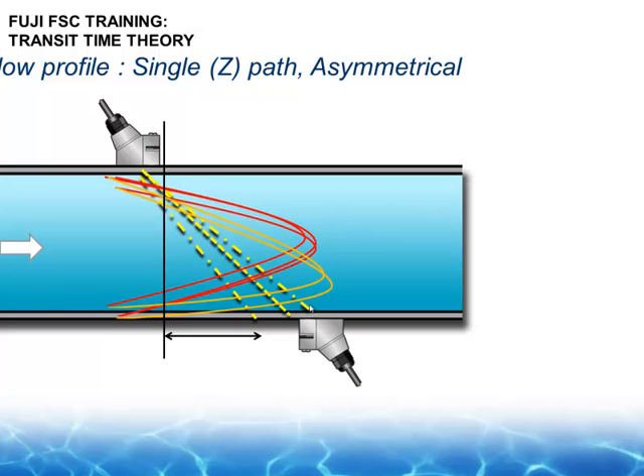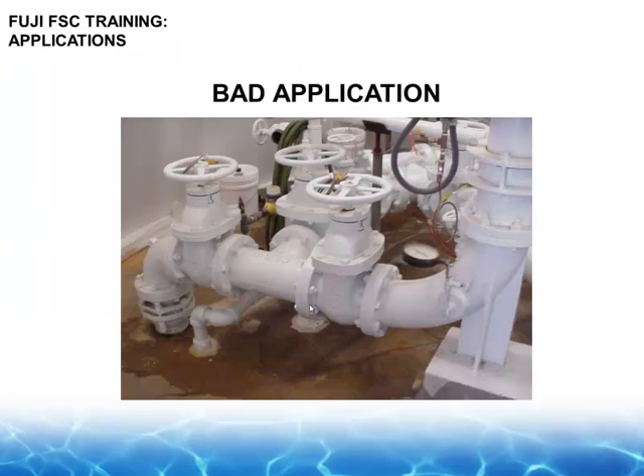So for spot checking, that would be an absolute nightmare. For a dedicated installation, you would actually lose your signal. So you need your straight run of pipe for optimum performance, especially for a dedicated installation. And if you do it on a portable application, you may be moving your transducer around, but you're not going to get the accuracies you're trying to achieve there. And this is what I usually get when I hop in the car and drive 200 miles to do a flow survey for somebody without pre-qualifying the application.